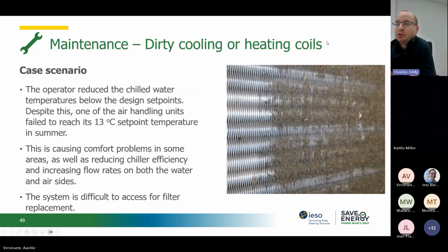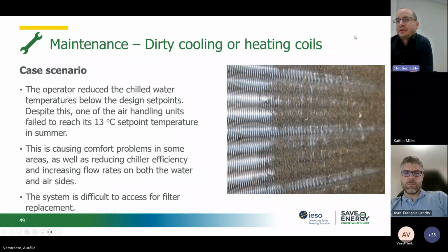Another maintenance problem that we see quite often is dirty cooling or heating coils. In that case, the problem was detected because the operator was reducing the chilled water temperature below the design set points. He was doing that because the coils were completely dirty, as we can see in the picture. And despite this, one of the air handling units failed to reach the temperature set point in summer.